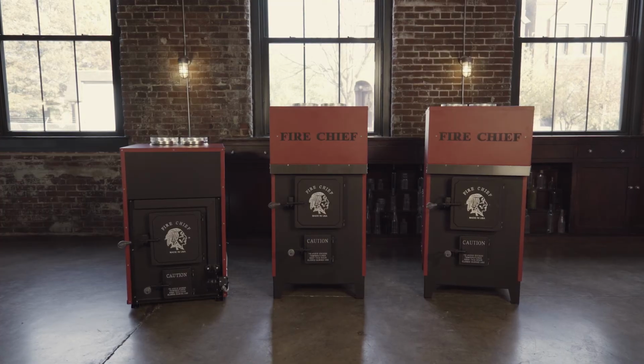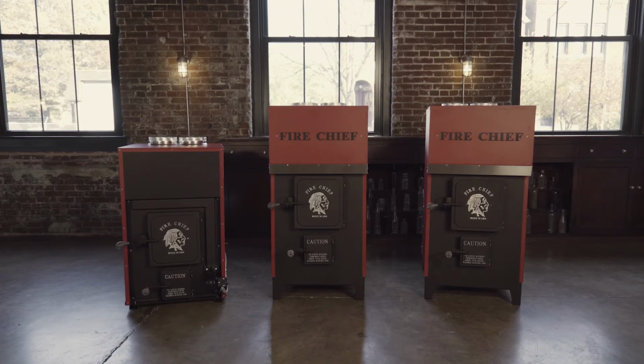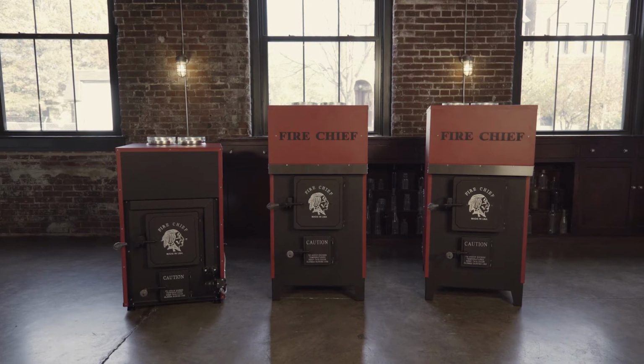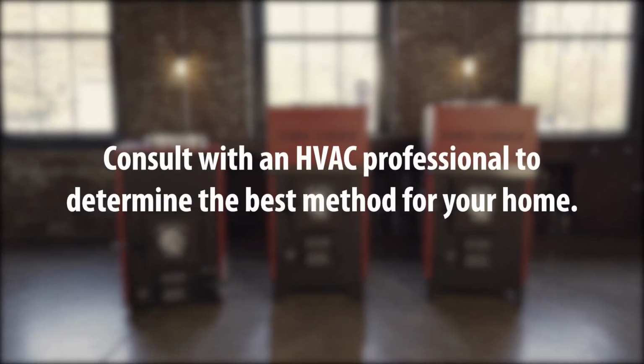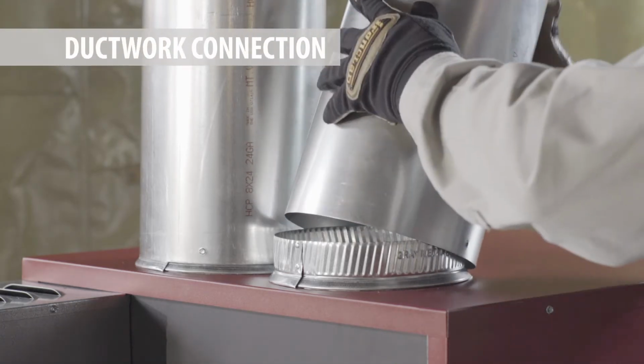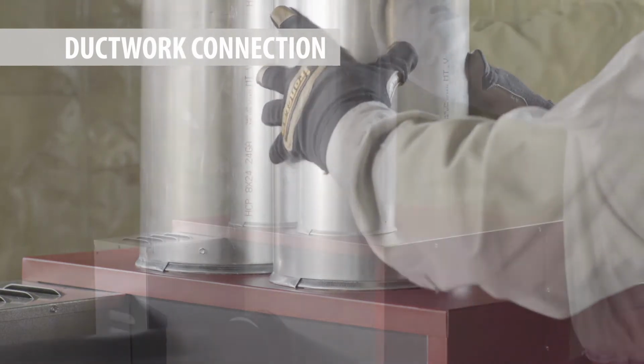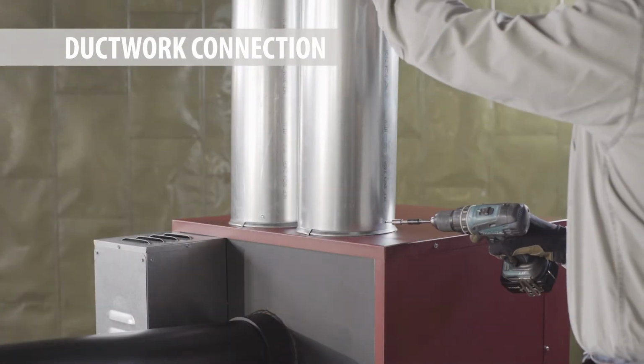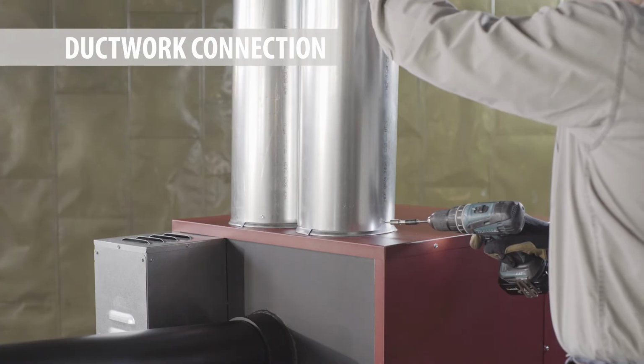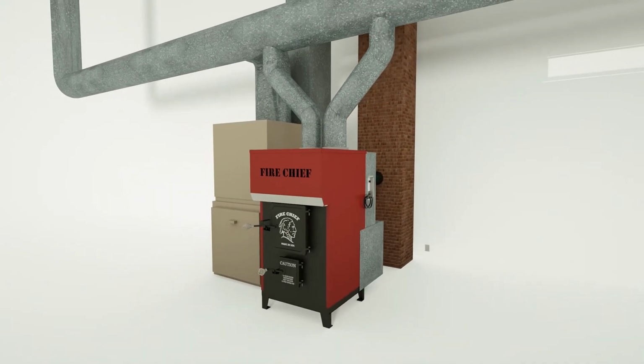Now, let's focus on connecting the distribution air for the furnace. There are many options to consider, and you may want to consult with an HVAC professional to determine the best method for your home. If you are connecting to existing ductwork, connect the 2 8-inch exits on the furnace to the trunk line. Never use more than a 45-degree elbow. The distribution air should be connected to the duct run at an angle and directed downstream to ensure proper airflow. Connecting to the trunk line will provide even airflow throughout your home.